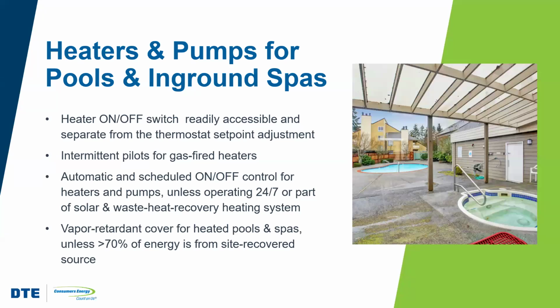For homes with heated in-ground pools and spas, unless the heater is using a heat pump or a solar energy source, there should be a vapor retardant cover for the pool or spa to reduce heat losses to the cooler air or loss of conditioned water through evaporation. And the heater should have a readily accessible on-off switch that does not require one to adjust the thermostat setting in order to turn the unit off. In other words, the on-off switch cannot be a knob that goes from 0 heat to heat level 10.